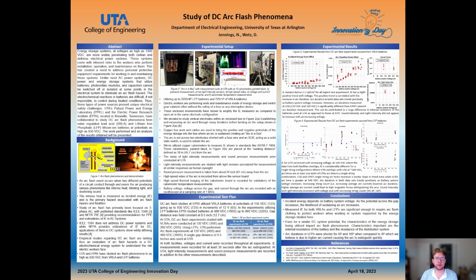IE does have a typical positive trend with voltage, and this is most likely correlated with the increase in arc duration. Arc duration in both datasets from UTA and EPRI did increase. However, the arc duration from UTA was much higher than similar arc voltages from EPRI. This is most likely due to the internal resistance difference between the batteries measured at UTA and batteries utilized at EPRI. The sound level and light intensity measurements studied at UTA did not vary or increase much with voltage, and we believe this is due to very low difference in the arc current studied.